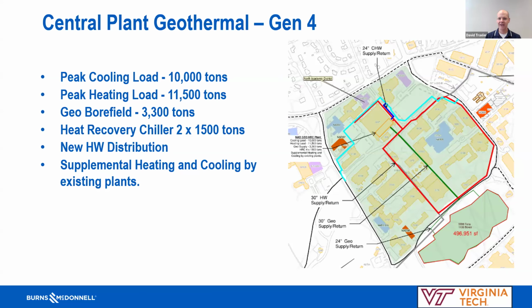I'll start with the academic district of campus. This area mostly has central utilities to its buildings. The peak cooling load is 10,000 tons, and the peak heating load is 11,500 tons—you don't normally refer to tons for heating, but this gives the same units to compare the magnitude of heating and cooling loads. The geothermal bore field can provide about 3,300 tons, and we have two heat recovery chillers at 1,500 tons each.